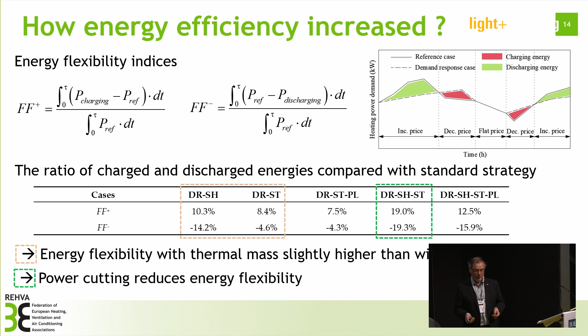Okay, then I have another use case here, which is a little bit more complex building. It's a hybrid heating system. In this case, there is a ground source heat pump together with district heating integrated there. So this is how the building looks. It's about a 40,000 square meter building, and it has a district heating connection, but a major part of the energy comes from the ground source system, where we have 47 boreholes with an average depth of about 320 meters. That is quite typical in Finland. Almost the whole area of the lot is suitable for these wells. In this case, the heat pump power is about 800 kilowatts, and the district heating power demand is 1,680 kilowatts. So they work in parallel.